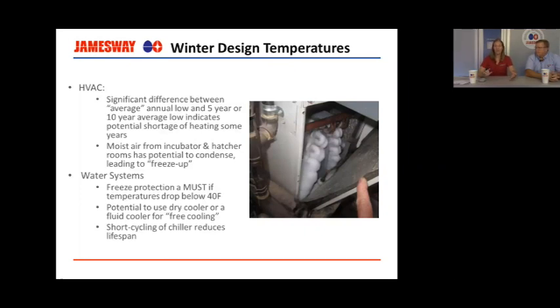And then you also have, in these situations, the ability to use a fluid cooler for free cooling. So what that does is it uses that cold outside air instead of using a refrigeration cycle to actually chill your chilled water. It's a big energy savings. And not only is it an energy savings, but it actually increases the lifespan of your chiller because you're not forcing it to come on for very short cycles throughout the winter.